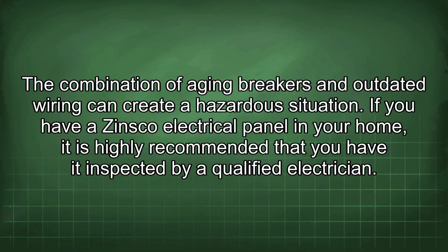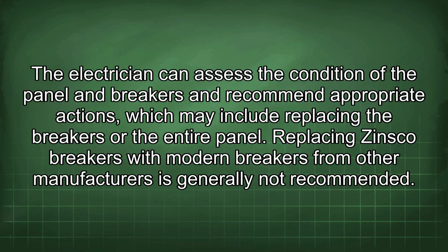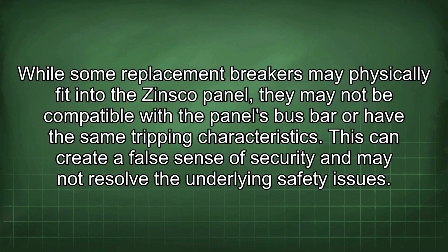If you have a Zinsco electrical panel in your home, it is highly recommended that you have it inspected by a qualified electrician. The electrician can assess the condition of the panel and breakers and recommend appropriate actions, which may include replacing the breakers or the entire panel. Replacing Zinsco breakers with modern breakers from other manufacturers is generally not recommended. While some replacement breakers may physically fit into the Zinsco panel, they may not be compatible with the panel's bus bar or have the same tripping characteristics. This can create a false sense of security and may not resolve the underlying safety issues.